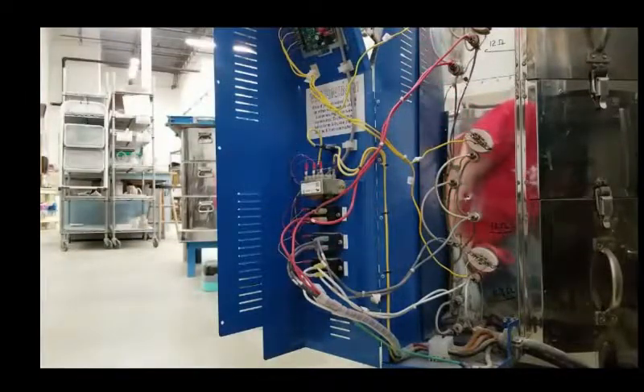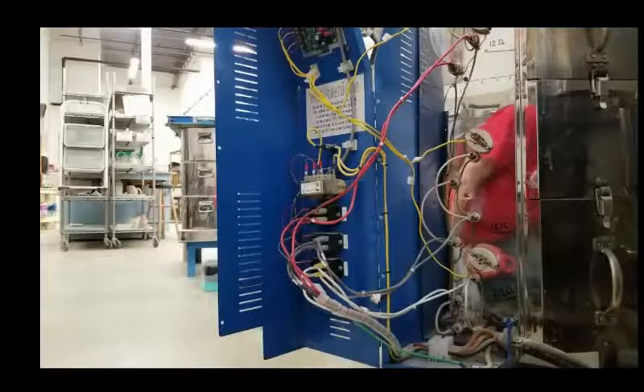So then we would suspect either an open element or a bad relay, and if we had already measured the resistance on our elements, we'd know it's not open because we got 12 ohms like we're supposed to. So then it would be the relay. But now we're going to do a little bit more.